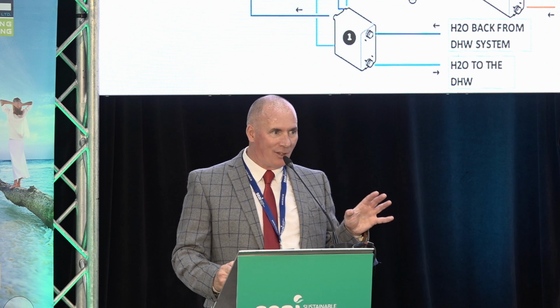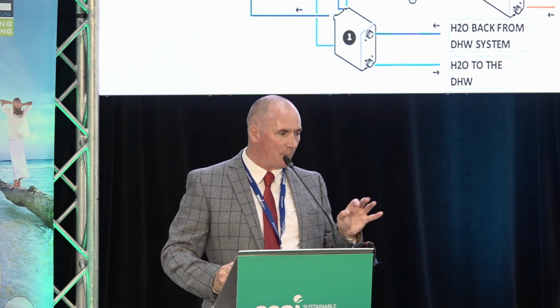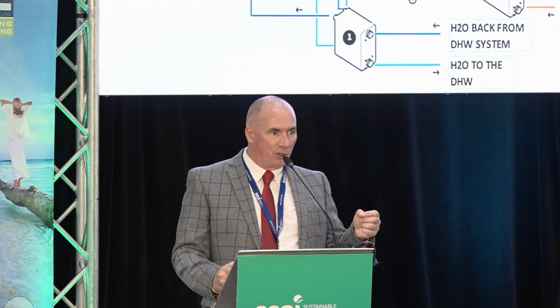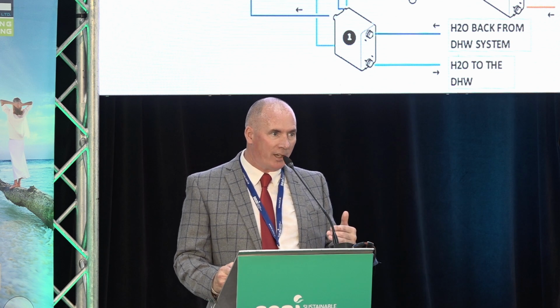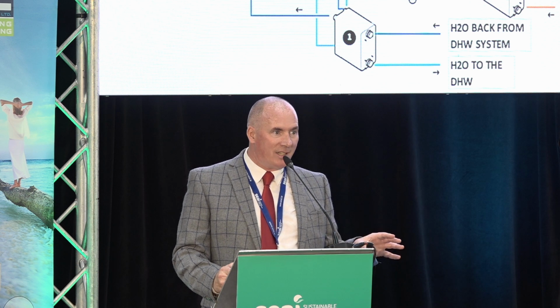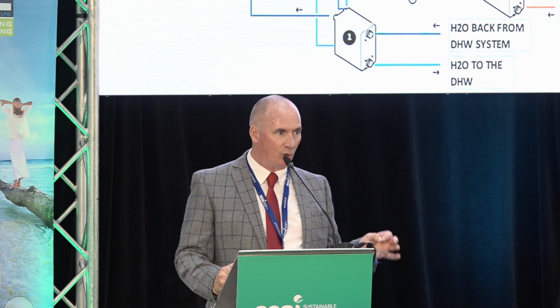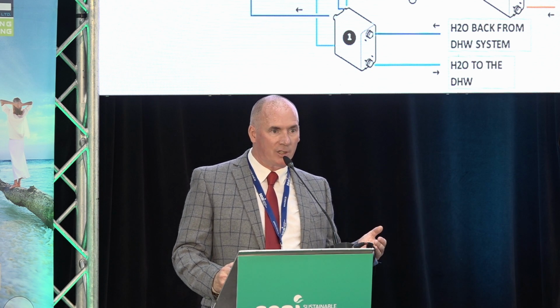Now, some engineers will criticize me for saying that because design criteria comes into play, but again, we're keeping it simplistic. So now, again, you have a new term called TER, total efficiency ratio, but it's the same, what you get out versus what you put in. In this mode of operation, we have a TER of 7, more than double the energy efficiency ratio in cooling mode, okay? That is the main reason multifunctional heat pumps are now very, very common.